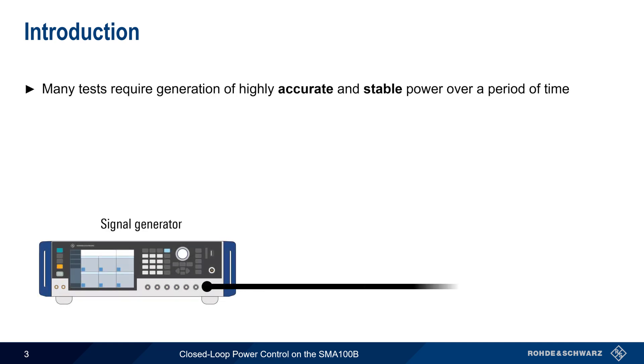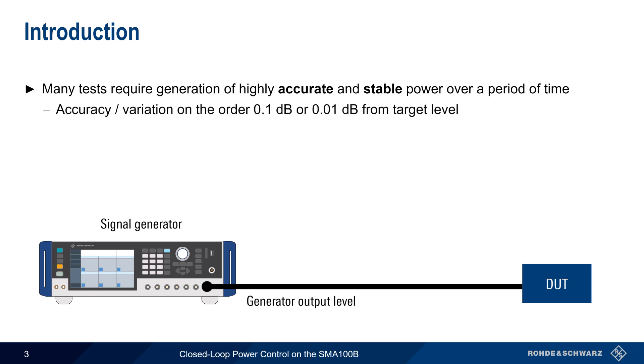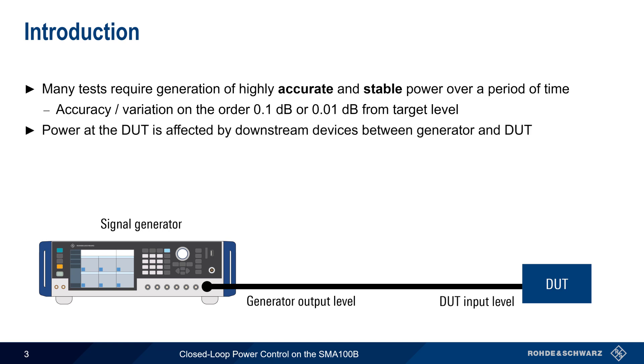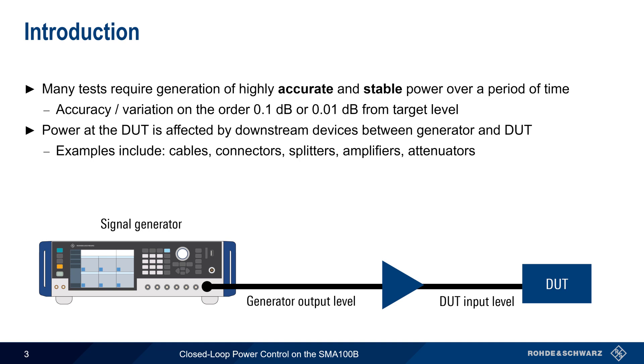Many RF testing scenarios require the generation of highly accurate and highly stable power over a period of time. The required degree of accuracy will vary by application, but accuracy on the order of tenths or even hundredths of a dB is often desirable. Although modern signal generators can easily meet this requirement, the power at the input of the DUT is affected by devices between the generator output and the DUT, such as cables, connectors, amplifiers, etc.